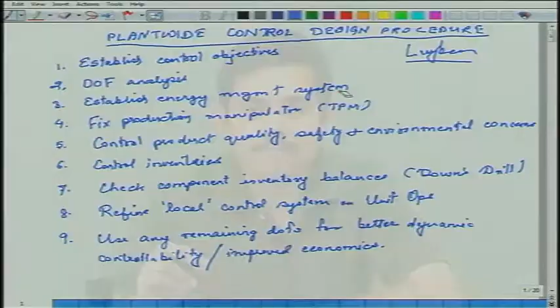Nevertheless, the plant-wide control system, because some mistakes can happen in terms of putting in place a control system that does not respect overall component inventory balance for at least one component, or sometimes maybe even total material balance. It is important to check that whatever control system you have put in place, it respects material balance. Everything that is coming into the process either gets reacted away or finds a way out, right. Double check that. So, step number 7 is essentially double checking this, that a mistake has not been made, because if a mistake has been made, that control system is doomed. Guaranteed something will build up or something will deplete, and then you will have to take a shutdown, okay, guaranteed. So, it is important to stress point number 7.